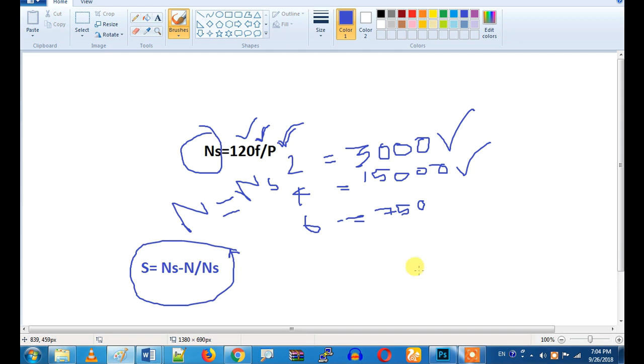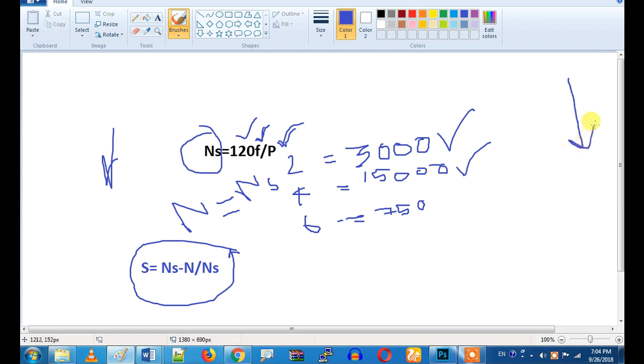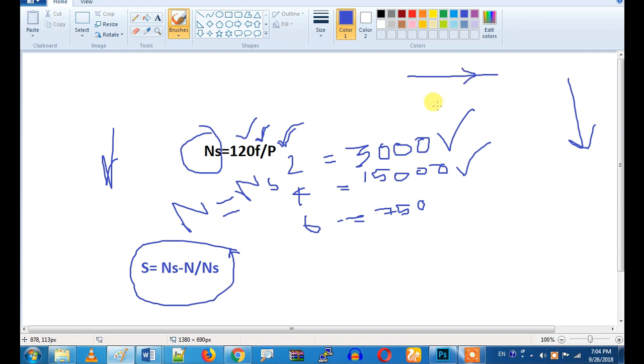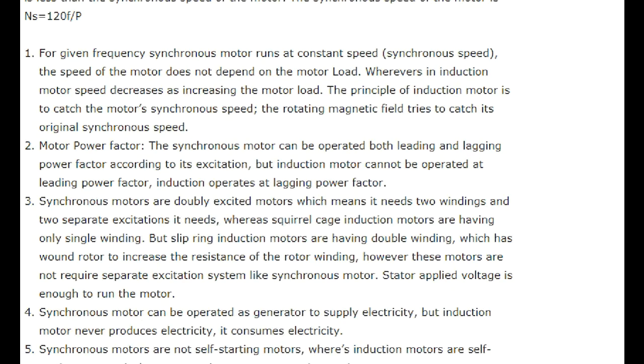What is the next difference? Load. In an induction motor, if you increase the load, the current increases and the RPM drops. In a synchronous motor, if you increase the load, the RPM remains constant, but the current increases. The RPM is constant, but the power factor changes.